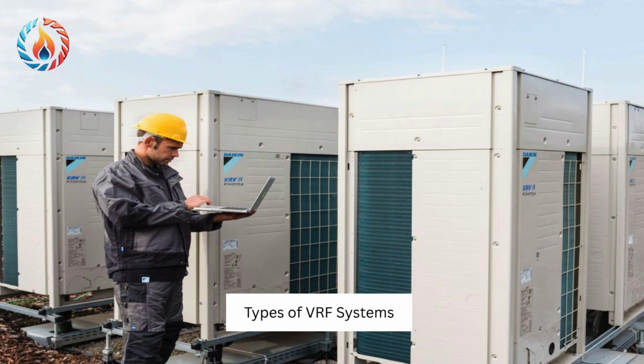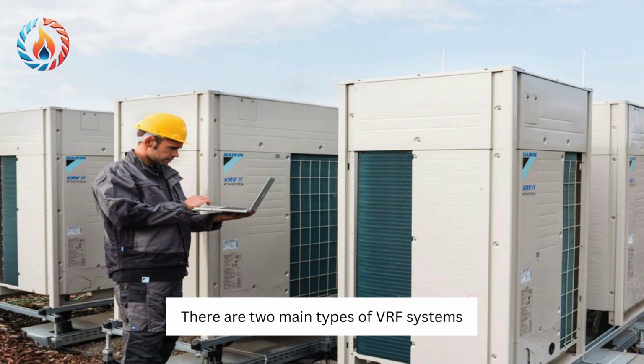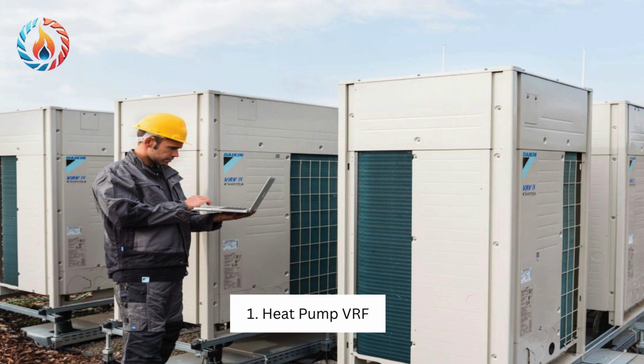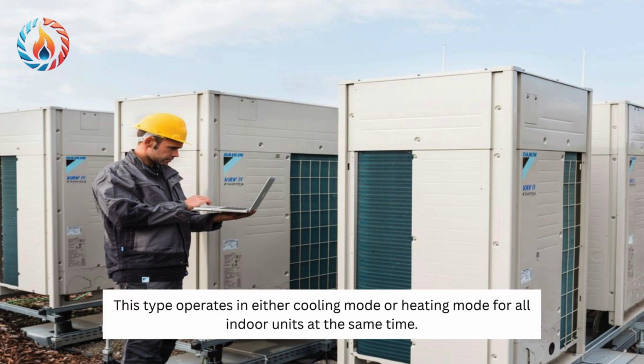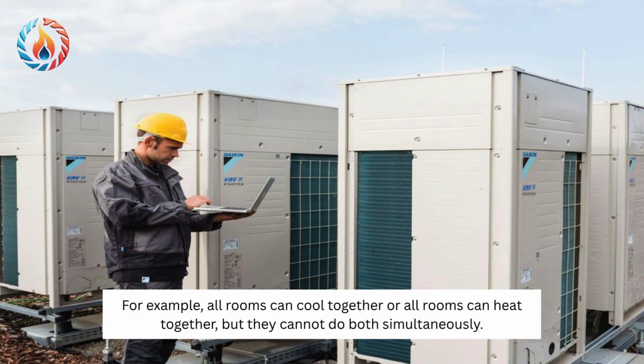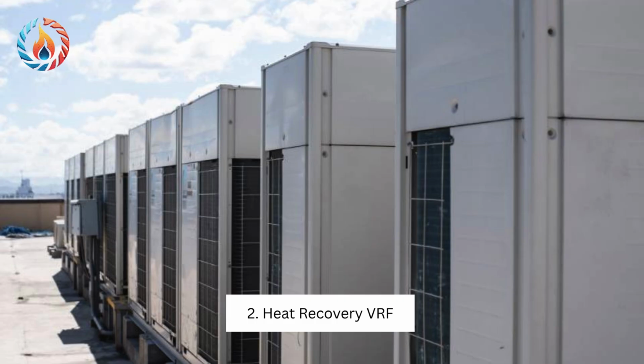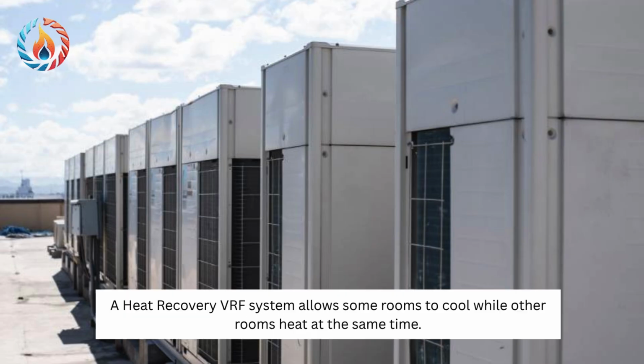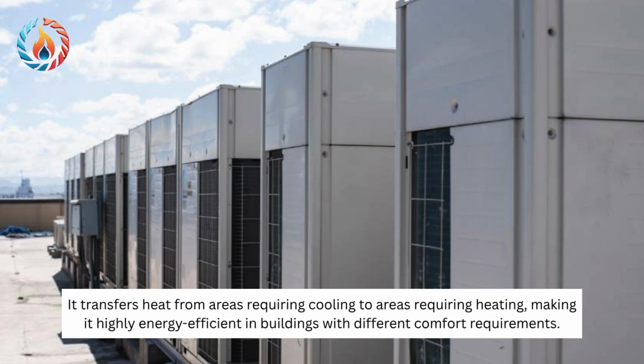Types of VRF systems. There are two main types of VRF systems. One, heat pump VRF. This type operates in either cooling mode or heating mode for all indoor units at the same time. For example, all rooms can cool together or all rooms can heat together, but they cannot do both simultaneously. Two, heat recovery VRF. A heat recovery VRF system allows some rooms to cool while other rooms heat at the same time. It transfers heat from areas requiring cooling to areas requiring heating, making it highly energy efficient in buildings with different comfort requirements.